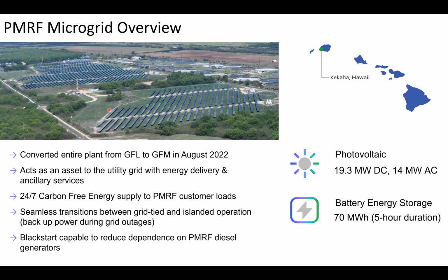We also combine that on top of the dispatch with ancillary services such as frequency and voltage ride-throughs for our converters to remain online for a longer duration to help support the grid. We also provide active and reactive power support or frequency voltage regulation.